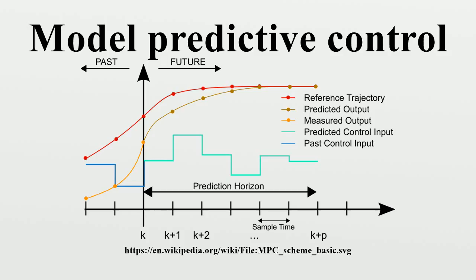Common dynamic characteristics that are difficult for PID controllers include large time delays and high-order dynamics. MPC models predict the change in the dependent variables of the modeled system that will be caused by changes in the independent variables.